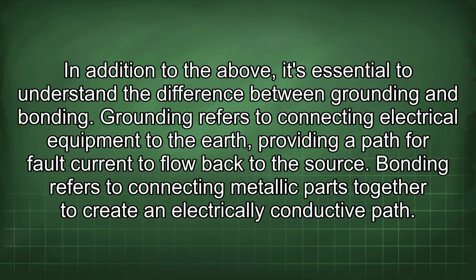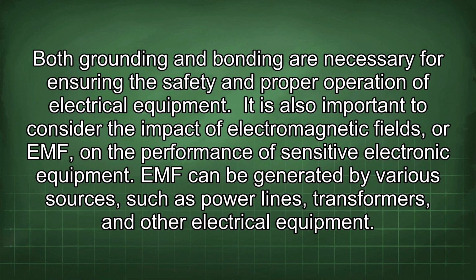In addition to the above, it's essential to understand the difference between grounding and bonding. Grounding refers to connecting electrical equipment to the earth, providing a path for fault current to flow back to the source. Bonding refers to connecting metallic parts together to create an electrically conductive path. Both grounding and bonding are necessary for ensuring the safety and proper operation of electrical equipment.